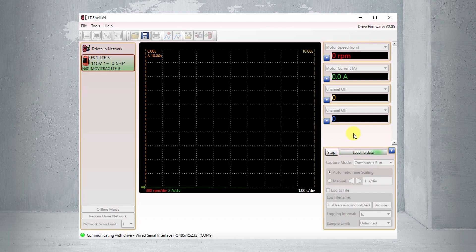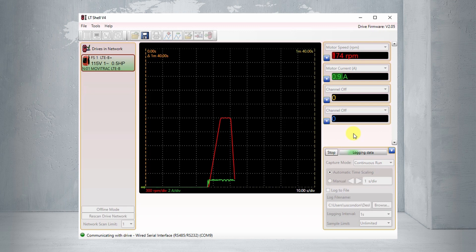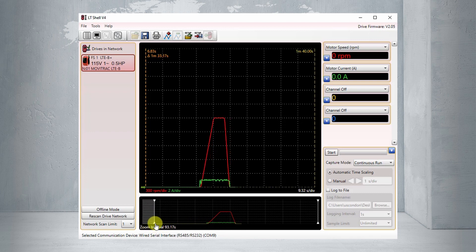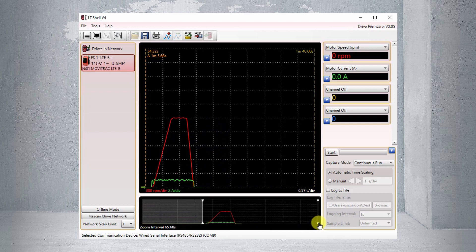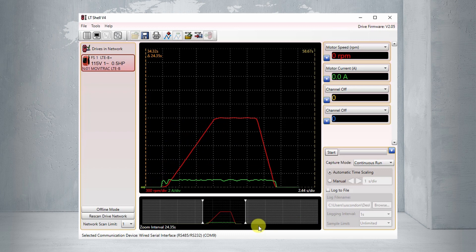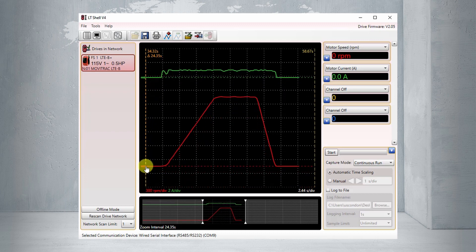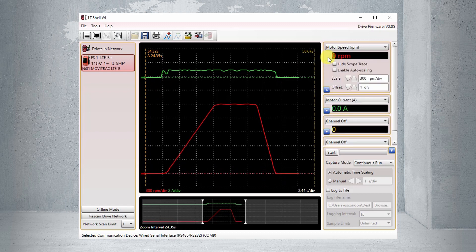I'll click the Start button — the scope starts acquiring data. You can see the trace is down at the bottom of the screen, endlessly collecting data. We're ramping up — it's taking a while because we have a pretty slow ramp. We're up to 1500 RPM. I'll turn the switch off and click Stop to stop capturing data. Looking at the bottom of the screen, this is the entire capture buffer and the data we're interested in is in the middle. I'll zoom in by moving the sliders, which restricts what's being displayed in the larger screen above. I'll also separate the traces by grabbing the green arrow and dragging motor current above motor speed.